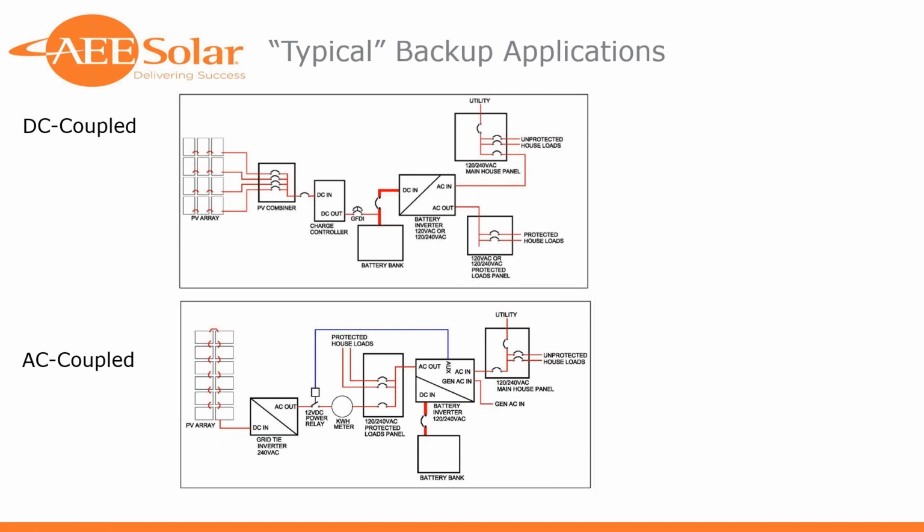So the biggest drawback to an AC coupled system where you don't have active curtailment is it's possible to have a scenario where this battery bank cycles frequently. What I mean by that is, because we've effectively got a PV inverter with an on-off switch and not a throttle, the PV inverter will continue to harvest wattage as long as it's connected to an AC source and as long as there's production.